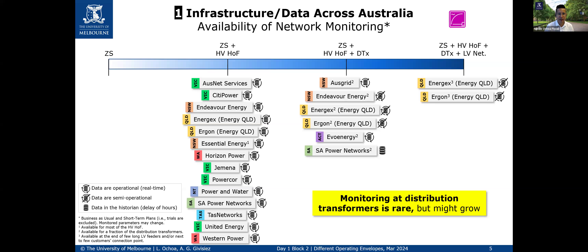In terms of network monitoring, it's very common to have substation or primary substation monitoring going to SCADA. Most companies in Australia have that. Some go beyond — monitoring in parts of the high-voltage feeder or at the head of the feeder, and also at distribution transformers. Some companies in Australia are starting to embrace more monitoring, particularly at the transformer level. There are even some companies with monitoring down to the low-voltage feeders, which is great but still rare. Distribution transformer monitors are very rare, though they may grow in the future.